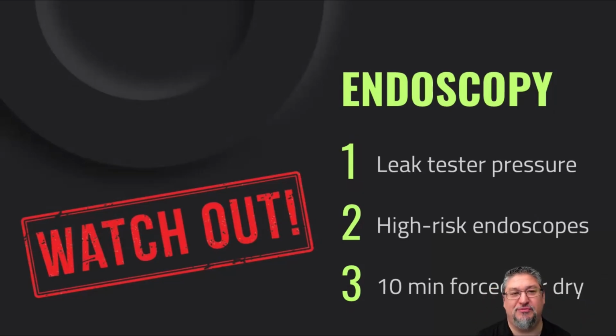Now, the newer machines, if you have one of these new ones that's more computerized, they actually do have a self-test functionality. But if you have one of the older ones, the Olympus MU1 or one of those older units, or even the handheld pumps, if you have one of those leak testers, make sure you have a way to test the pressure output from those. It's an important step that's getting missed, and I see it getting findings in facilities.